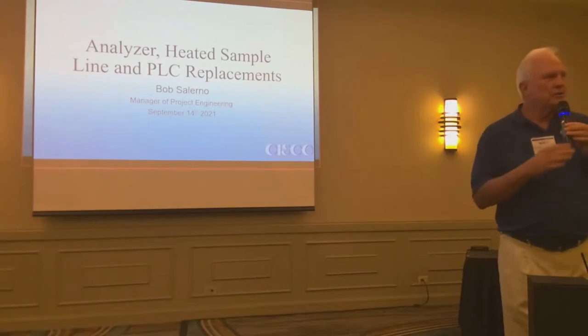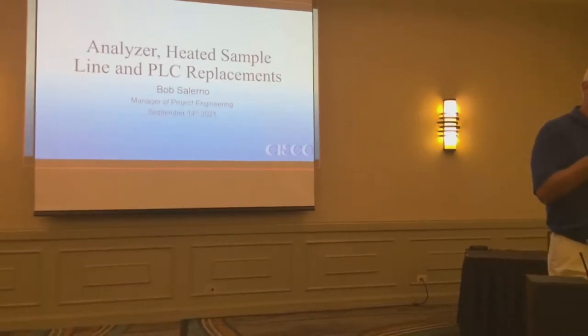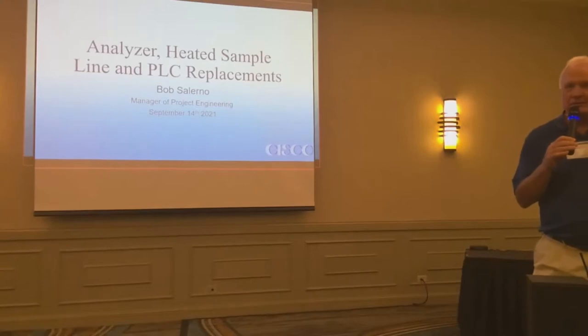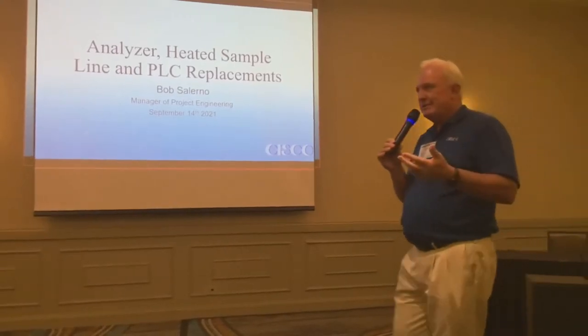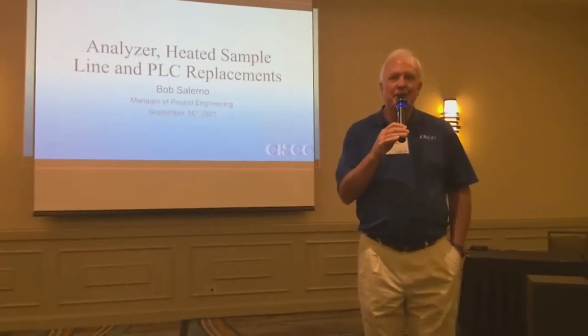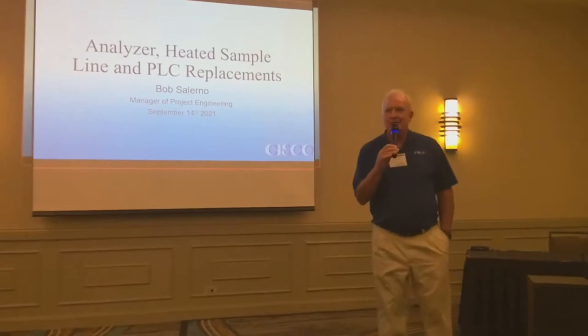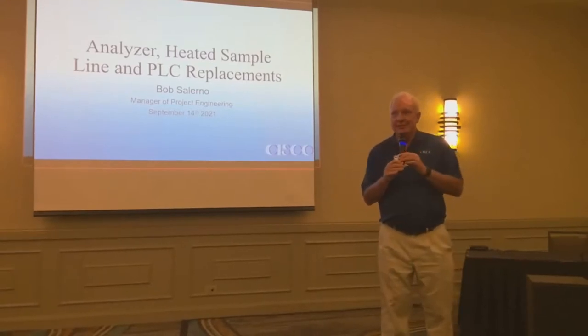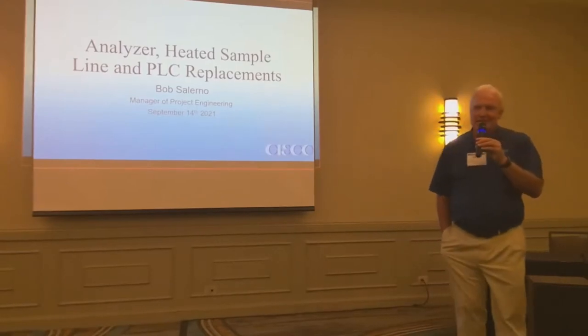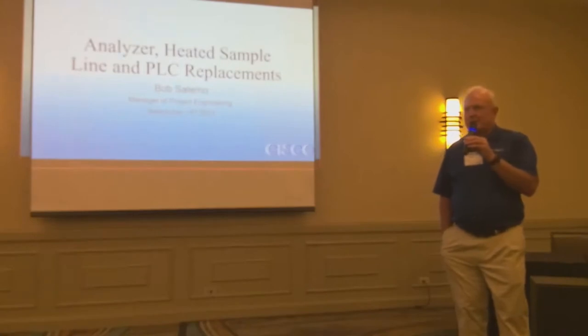We used to use only lines where the length could not be changed or altered more than a slight amount. A lot of our customers wanted to be able to cut off 100 feet. You're wasting money, by the way; they're $50, $60, $70 a foot. We had one site down in Texas that ordered 190 extra feet of heated sample line on one unit. I don't understand that. We can trim the lines to a certain extent, but we can't just hack them on. But what are the things you have to think about?